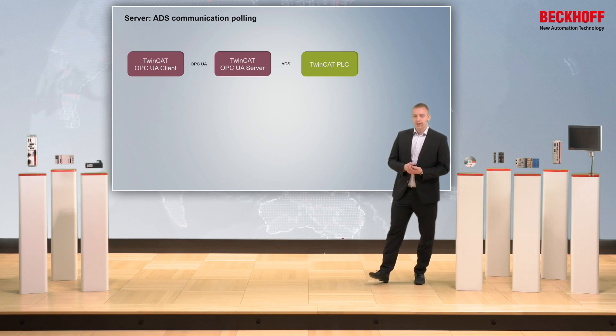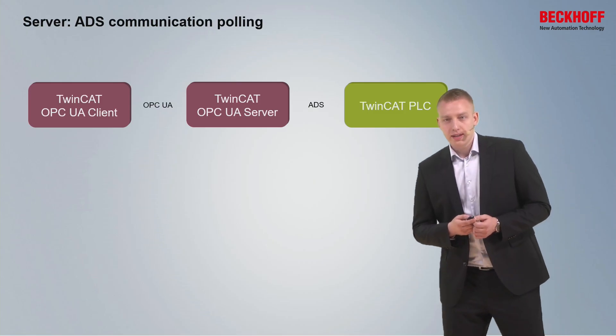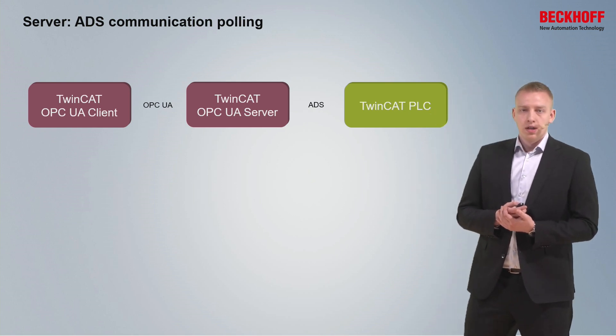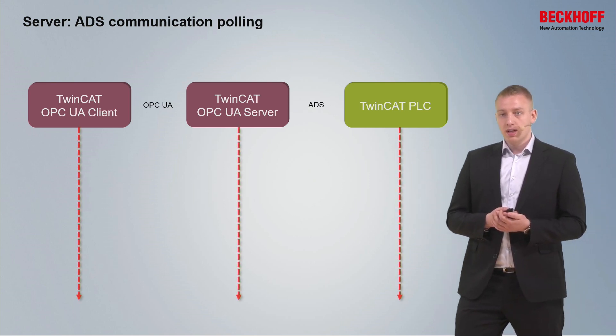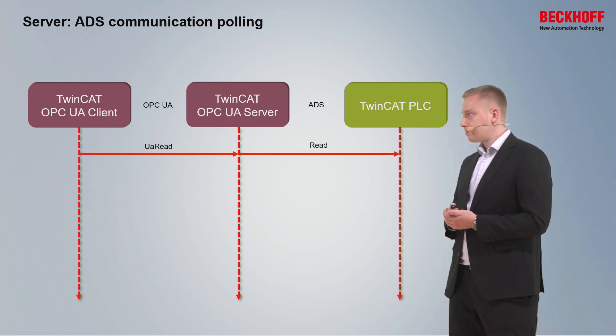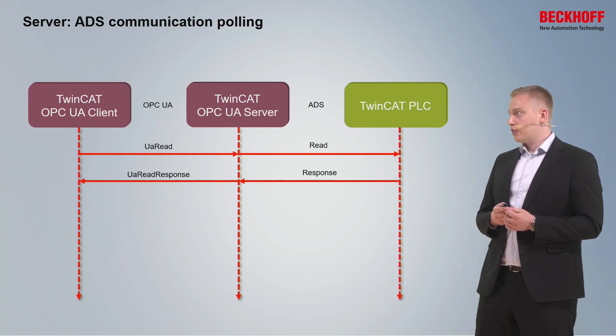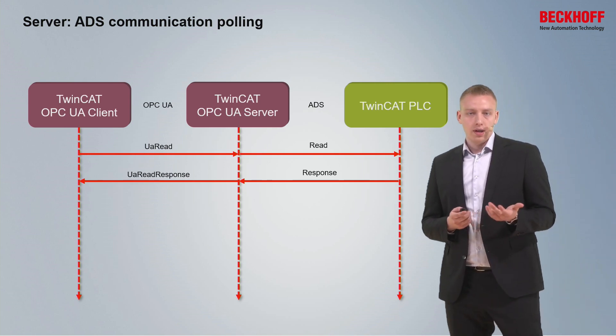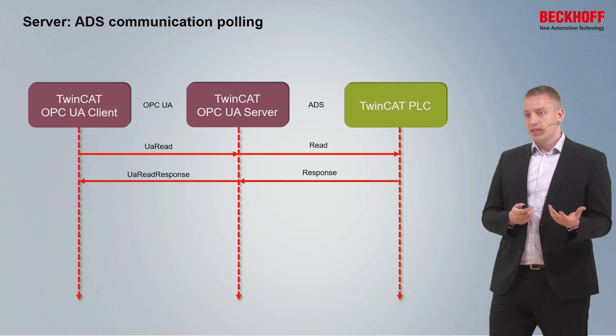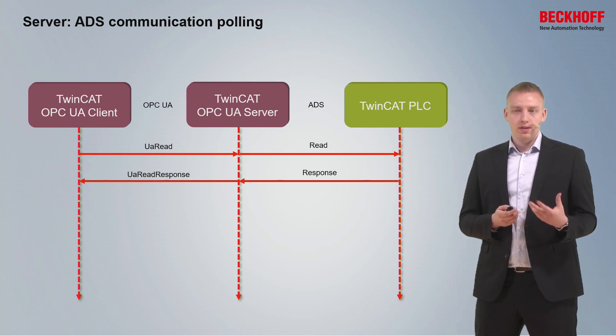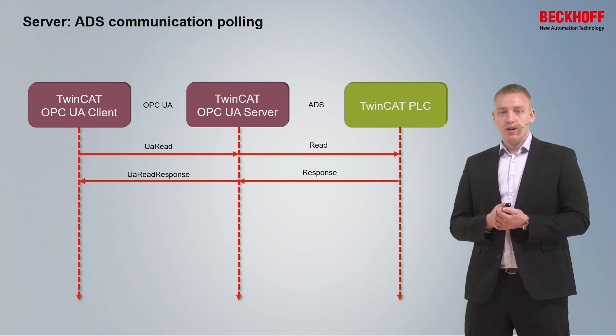The TwinCAT OPC UA server communicates with the PLC runtime via the ADS protocol. The first way of communication is polling: the OPC UA client sends read requests at a specified interval to the OPC UA server, which then communicates with the PLC runtime at the same interval. The disadvantage is that if a variable is not changing often, communication still takes place even when the variable's value hasn't changed. For such cases, OPC UA offers a more elegant approach: subscriptions.